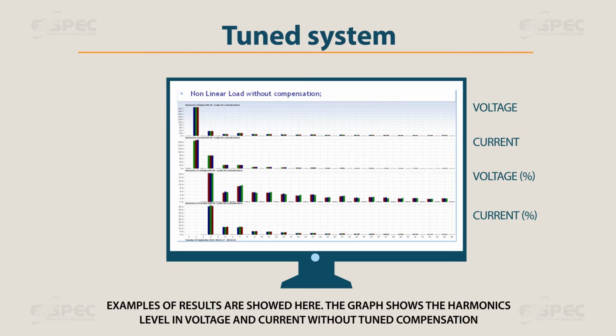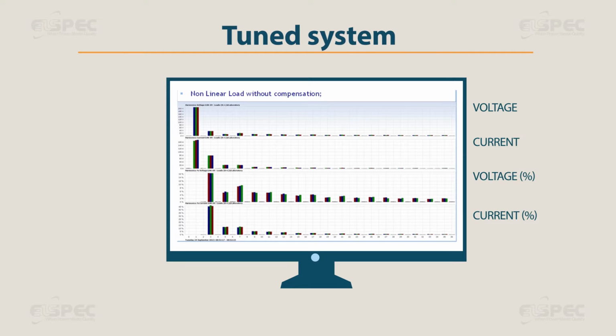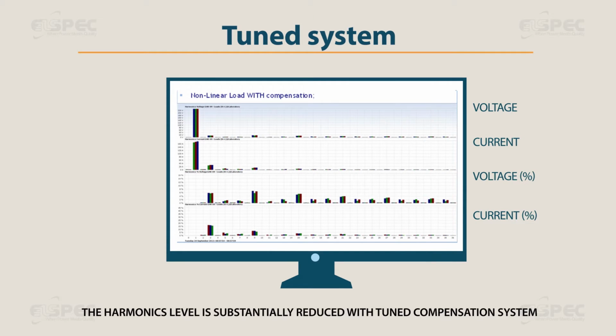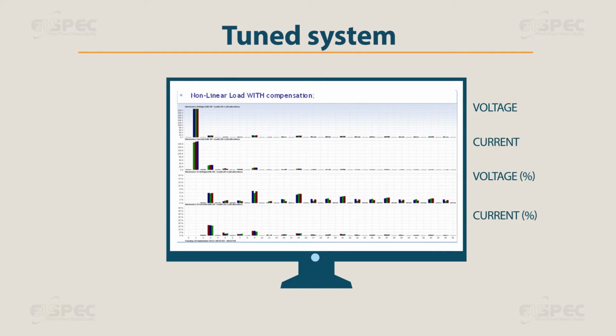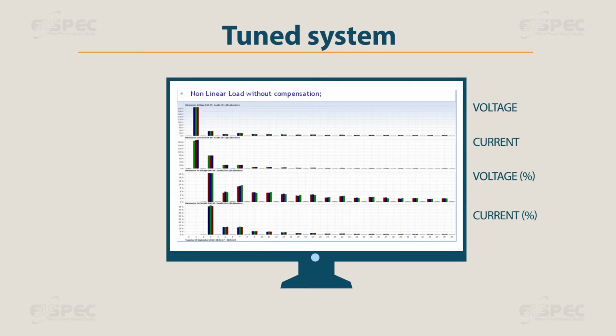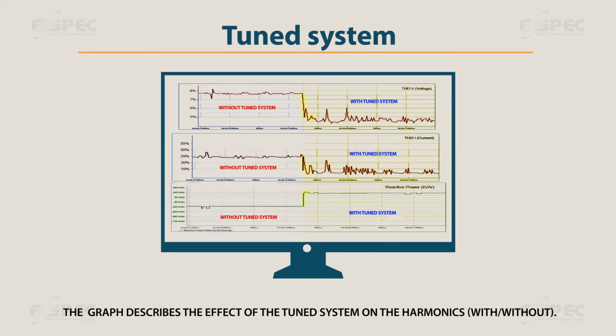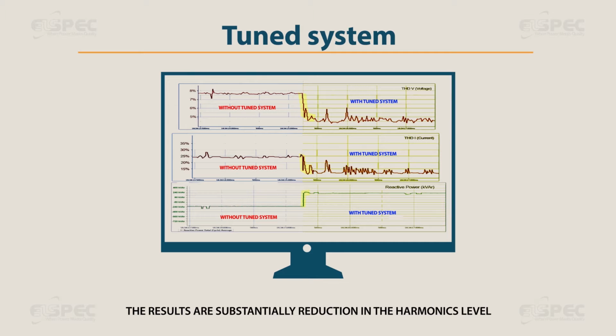Examples of results are shown here. The graph shows the harmonics level in voltage and current without tuned compensation. The harmonics level is substantially reduced with the tuned compensation system. Without compensation. The graph describes the effect of the tuned system on the harmonics, with and without. The result is a substantial reduction in the harmonics level.